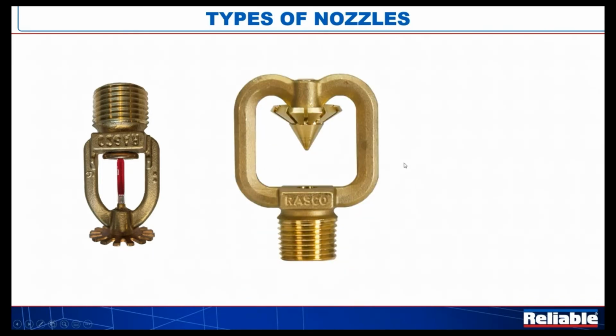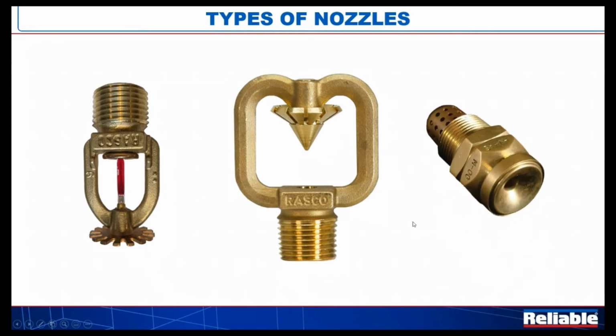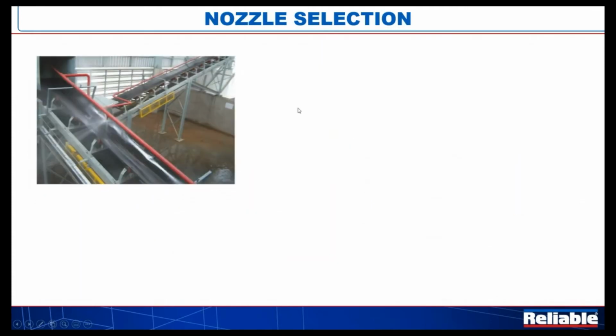We'll talk about some of these characteristics here in just a second. And then what's called the high velocity nozzle there on the right. And obviously, much like sprinklers, we have these available in different K factors and discharge angles particularly. We don't have that ability necessarily with the low velocity fire sprinkler, but we do very carefully shape the size and the shape of the cone that's doing the protection out of these other two.